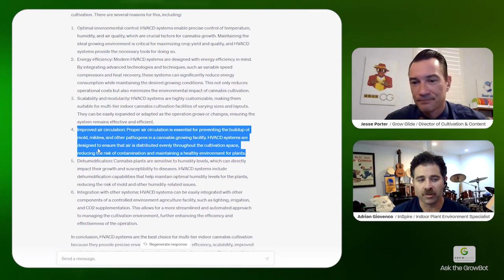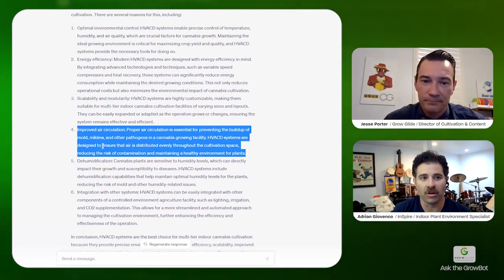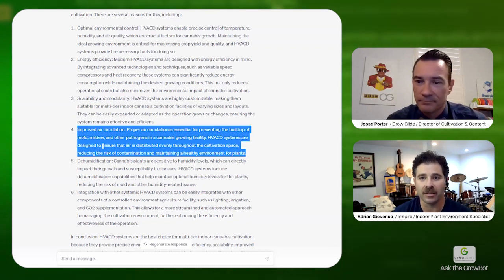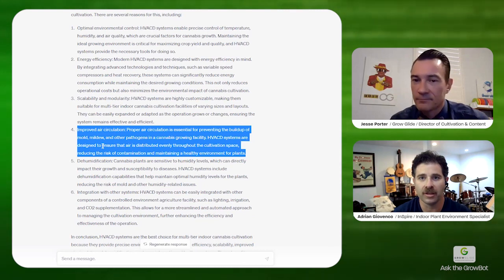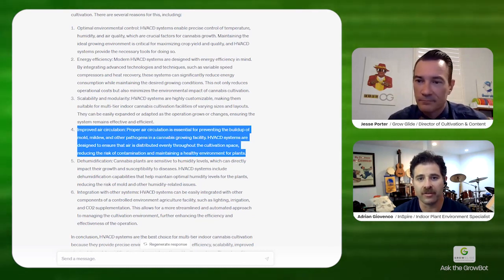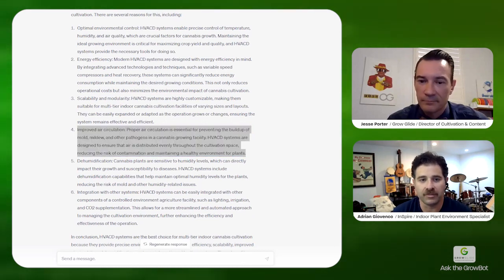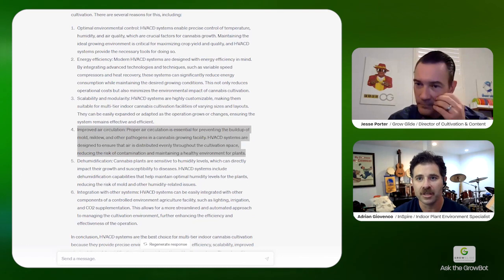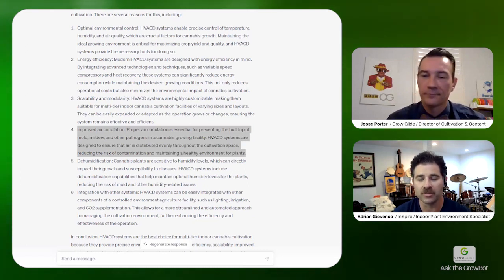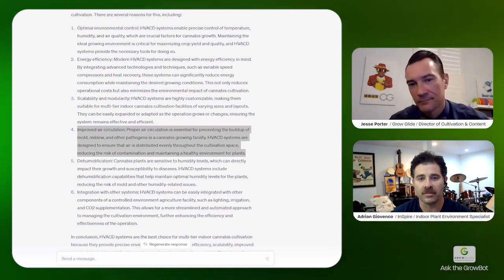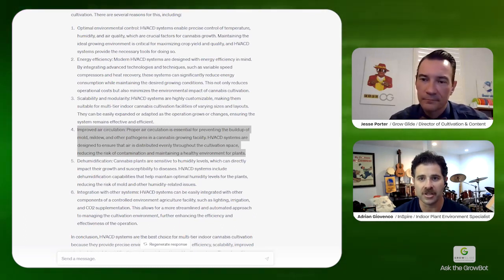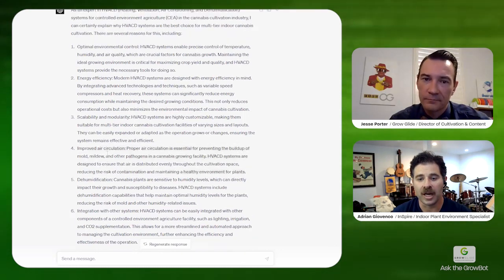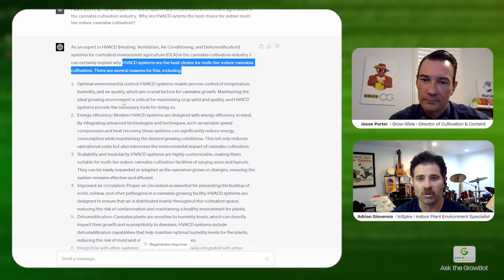Yeah, I think that's really where we see the need for multi-tier systems—you need to be able to deliver the air exactly where you want it and return it from exactly where you want it. That's really the big benefit of an engineered system. There's 10 different ways to skin that and put an engineered system together: multiple air handlers ganged together into a single duct, or multiple supplies or multiple returns. There's a bunch of different ways to do that, different levels and different types of systems that can get you there. But I think the common denominator is that you need to be able to control where that supply air goes and where the return air comes from.